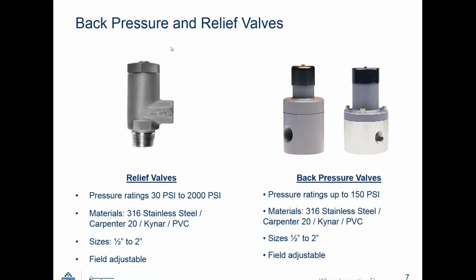the piping. The relief valves range from 30 psi to 2,000 psi. Materials: stainless steel, Carpenter 20, Kynar, and PVC. Now the pictured relief valve here is made in the 316 and Carpenter 20 design. The Kynar and PVC models look like the back pressure valves to your right. And the sizes are 1/2 inch to 2 inches, and are also field adjustable.